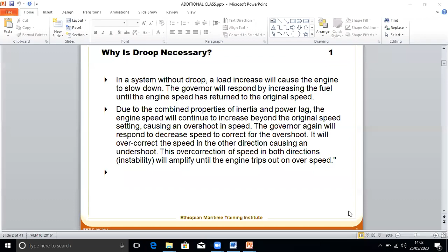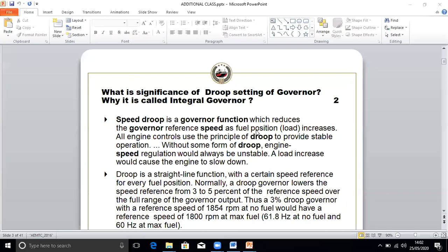Okay. So the second question is, why is this one called integral governor? What is the significance of droop? To observe the effect of droop, PMS has to be put in manual. As you load the generator, you can see when the load increases, the speed drops. So why is the speed dropping? Why does the generator speed decrease with increase in load?